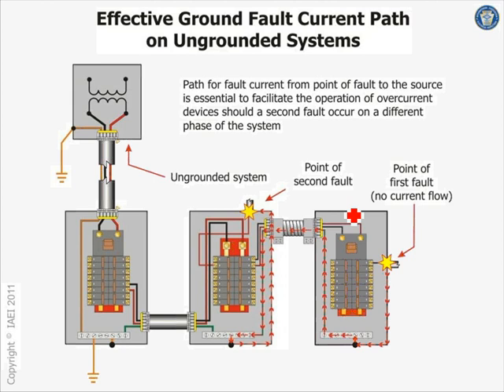Look at this system. Can you guys tell that this system is an ungrounded system? When I was green, it used to bug me. There is a major difference between the system being grounded and the equipment being grounded. Those are completely different things. My system here is any of these windings of the secondary of the transformer. Are there any windings connected to Mother Earth? No, this system is an ungrounded system. Do you see that the box where the transformer is sitting must be grounded? You have to ground the box. That's equipment grounding. So we grounded the box.